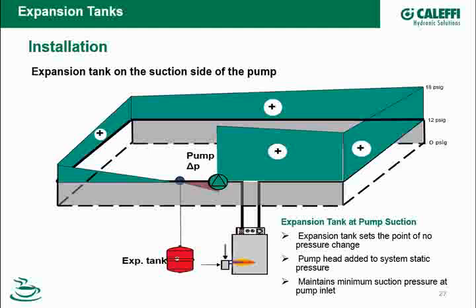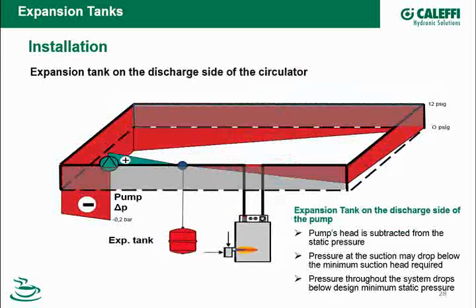The other thing it does: all circulators and pumps need a minimum suction pressure on the inlet of the pump. By putting the expansion tank on the suction side of the pump, it locks in the static pressure of the system and ensures I'm going to have proper inlet suction pressure. The end result is cavitation is not an issue. If I put the expansion tank on the discharge side of the pump, it would still generate the same differential pressure, or delta P, that it would in the exact same system. But now the discharge pressure of that pump is locked in to the static pressure of the system. If it's going to generate its delta P, the only way it can do it is for the suction pressure to drop. So a couple of things happen.